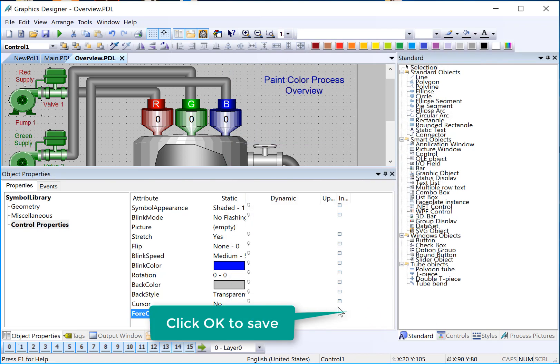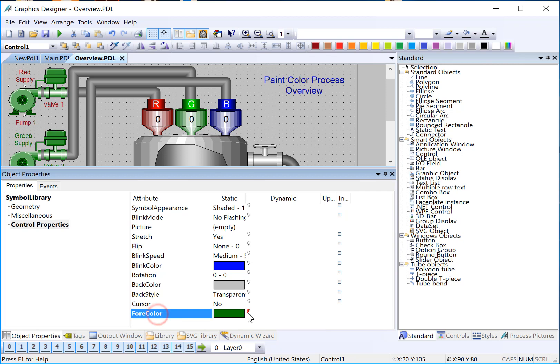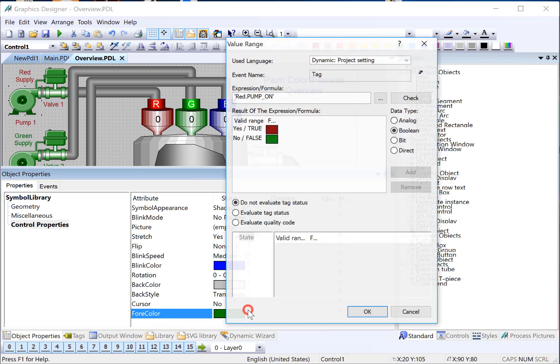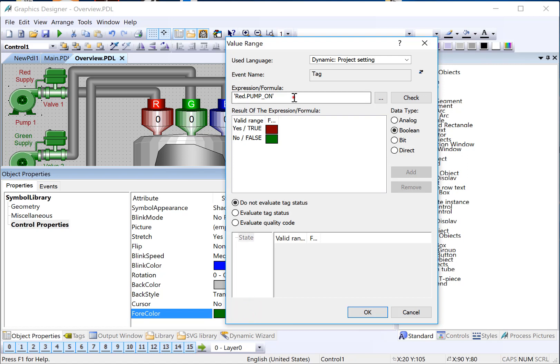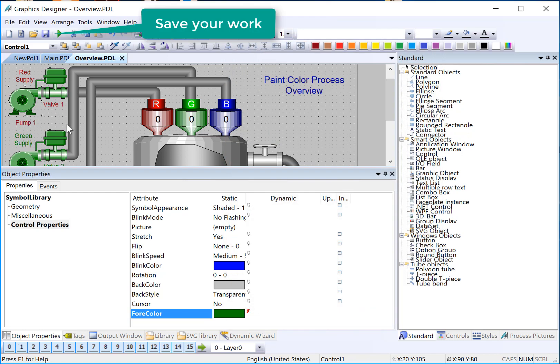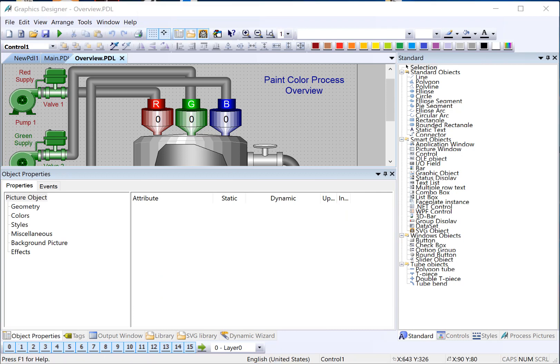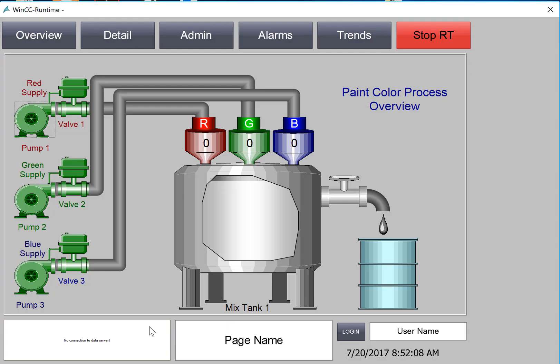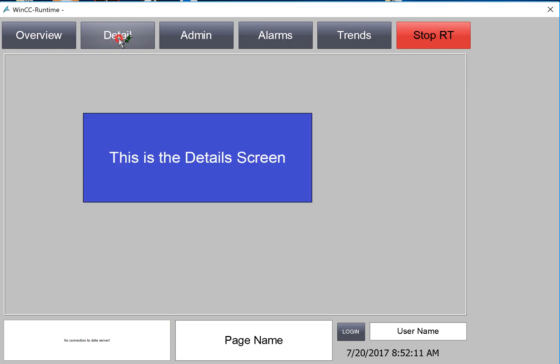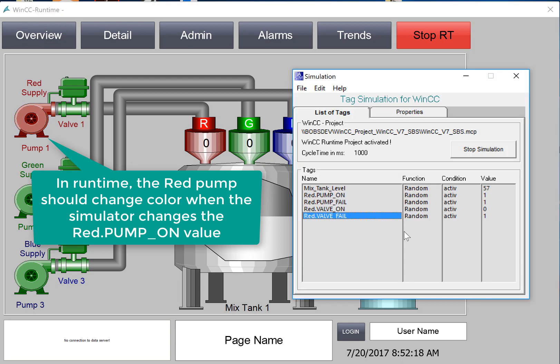So the way that we read this is the ForeColor property, which is now bold, by the way, you can see that it's bold. The ForeColor property is being controlled by this dynamic, and it's looking at the tag, and based on the value of the tag, we are setting this property. So if we want to see what this looks like, we can save. And my runtime window is still up. I don't have to hit runtime. I can just bring this up. And all I have to do is leave the page and come back. And we can see that this pump is going to change color based on our simulator.